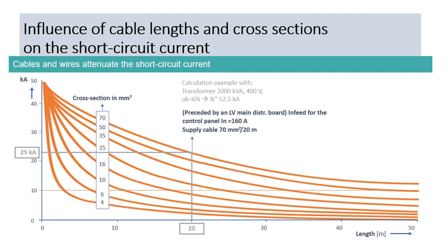My last slide. Before we do the calculation, I just wanted to talk about this. Here we're looking at the influence of cable lengths and cross sections on the short circuit current. The tool we're going to look at today will take into consideration attenuation.